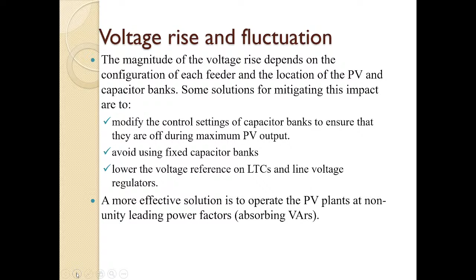Okay. So, the voltage rise phenomenon is a big problem in the system, and all these distribution companies are now facing problem due to this voltage rise. And the smart inverters, that is the solar inverters, if we make them smart, then they can also produce reactive power, and the reactive power they can absorb as well. So a coordination between the rise in voltage and the reactive power supplied or absorbed needs to be done, and that will give rise to the solution as well as give rise to having more and more solar power into the system. Next.